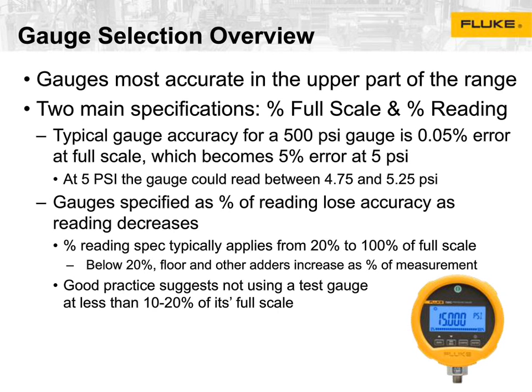You're going to see two main specifications from gauge manufacturers. Either percent full scale, which is a holdover from the analog days, when analog gauges were specified as percent full scale. But you're also starting to see percent reading, so a manufacturer might specify their gauges as an error as a percent of the reading they're giving. When you talk about full scale specifications, it's critical that you pick a gauge whose upper range is almost identical to where you're going to be working. If you're going to be working at 1500 psi most of the time, you want a gauge that's as close to 1500 psi as you can. So you'd either want a 1500 psi gauge or maybe a 2000 psi gauge if you can't get a 1500.